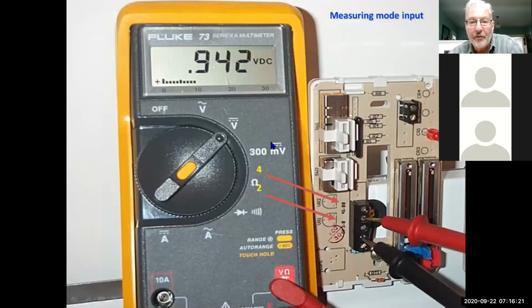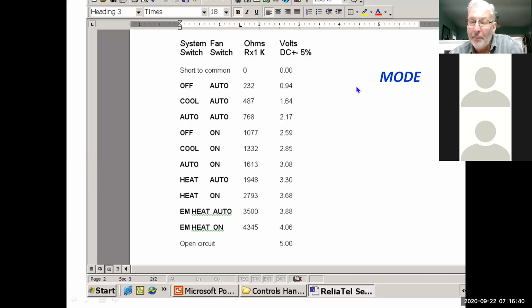Now, to test these DC circuits, you grab a voltmeter and go between pins 2 and 4. 2 is your common on these, and 4 is going to be your mode input. In this case, if you read 0.942 volts DC, and you go to the chart in the Reliatel book, 0.942 volts DC is right here. That tells us that the unit is in the off position and the fan is in the auto position. So every one of these values means something different to the board. If I turn the heat on and the fan on, I should read 3.68 volts. The board sees that voltage and it knows what to do. It's based on a DC voltage input.